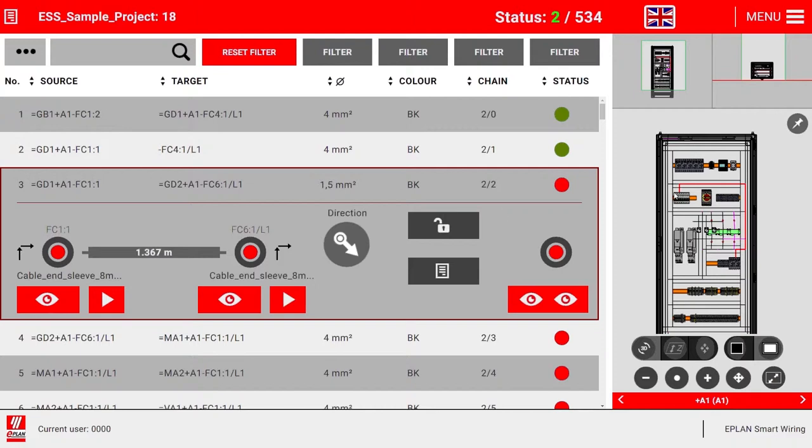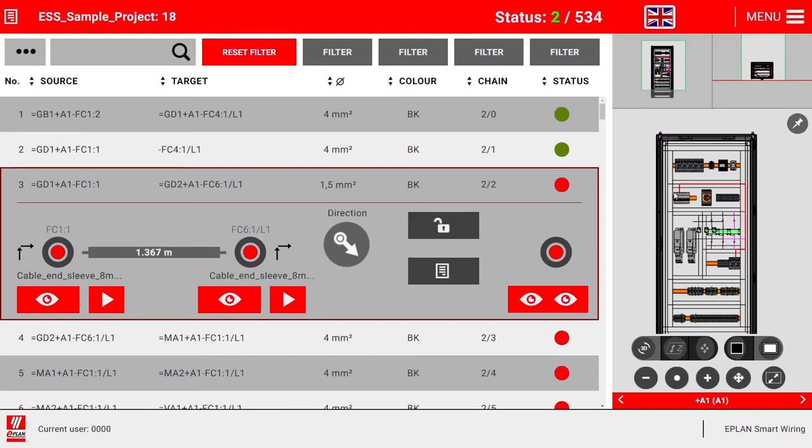This is really good for multi-units. Somebody wants three, five, or ten of these. If you have a left-handed wireman you may take one route, a right-handed wireman may take another. They may put wires in a different order so the panel looks very different as you put it together. But by following the simple rules inside here, you can get a less-experienced wireman and get ten panels exactly the same. When somebody opens a panel, they know exactly where the wires are going to route. You're taking decisions away from the technician because the panel builder has made those decisions, the person with the expertise and knowledge.